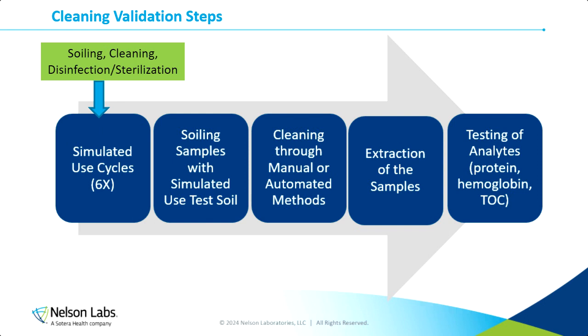This is where we would soil the samples with a soil that would mimic clinical use, what the device would see in a hospital or clinic setting, whether that is blood, mucus, or skin. After we soil the devices, we process them through the cleaning, typically a manual or automated method. We would validate manual and automated separately. Following the cleaning, we move to the extraction of the samples. There are multiple methods of extraction. We could manually shake it, swab it, or sonicate it, and really we are just performing that extraction using water. Then we would test those water extracts for endpoints such as protein, hemoglobin, or total organic carbon.